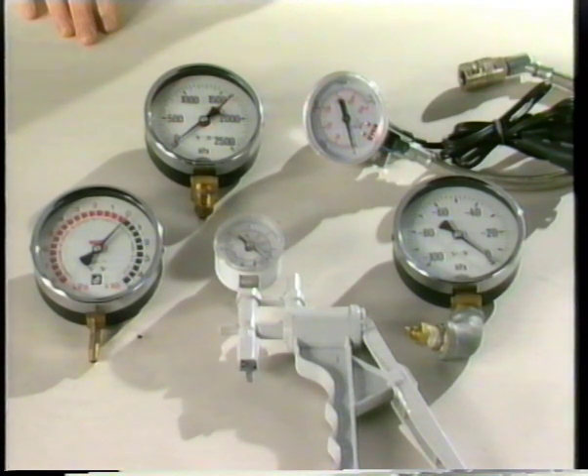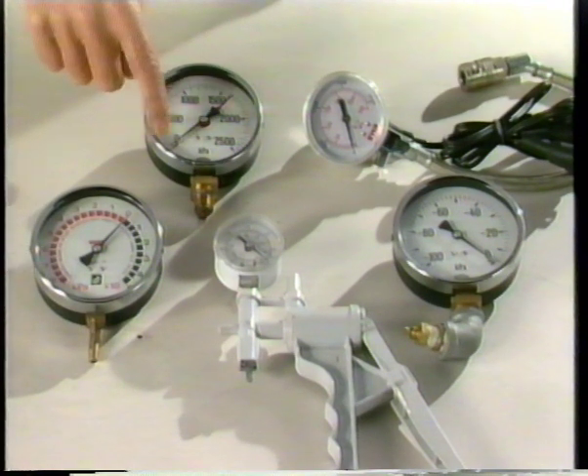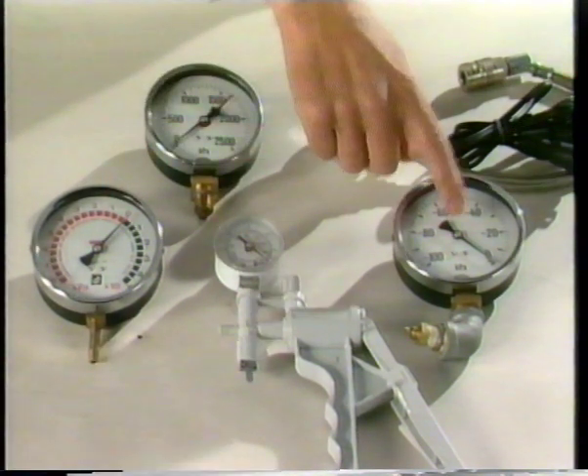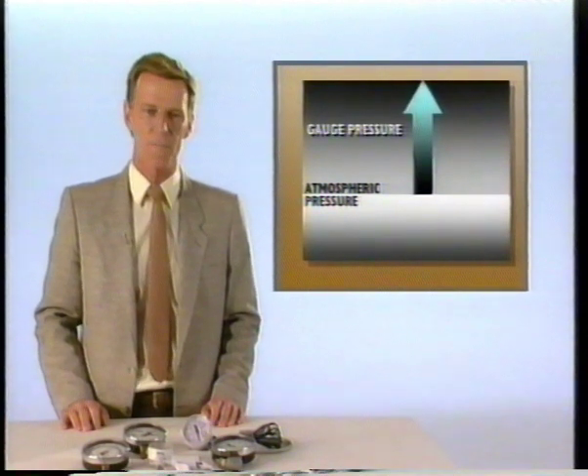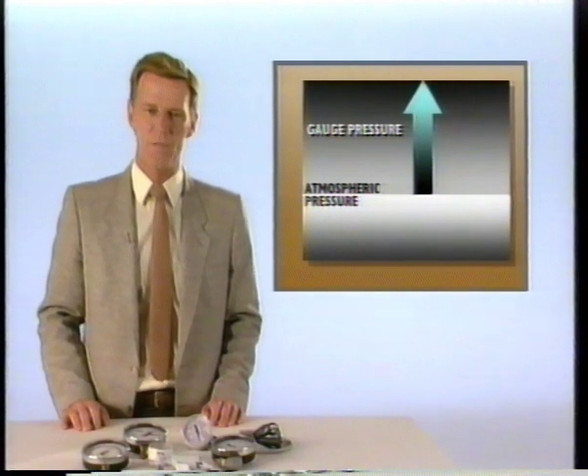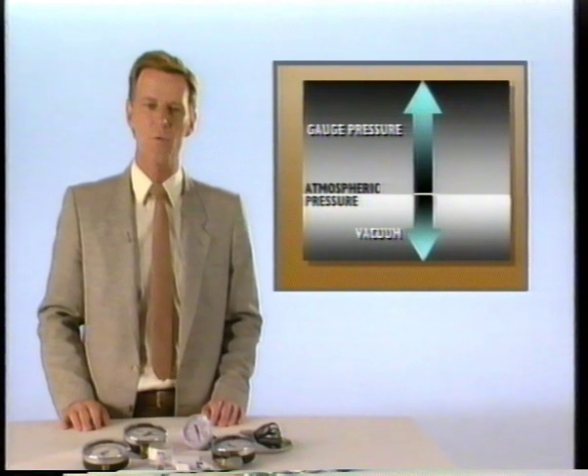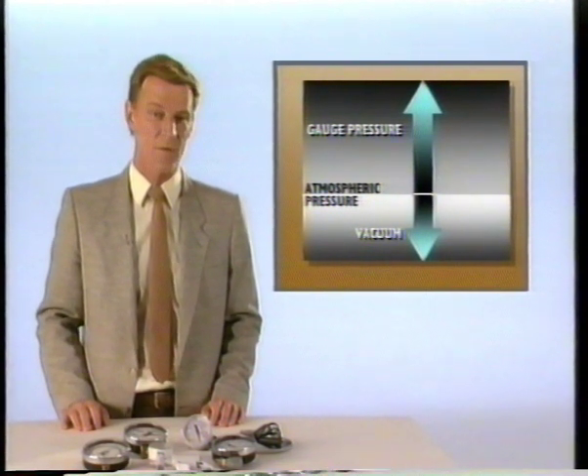It works like this. Most pressure gauges we have used in this country have always registered 0 when not connected. In actual fact, though, atmospheric pressure has still been applied to the gauge, but it has been calibrated this way for convenience. This type of gauge reading is referred to as gauge pressure. Reference to this graphic will show you what I mean. Everything above the atmospheric line is referred to as gauge pressure, and everything below the atmospheric line has been referred to as vacuum, down to a point where a perfect vacuum was achieved.